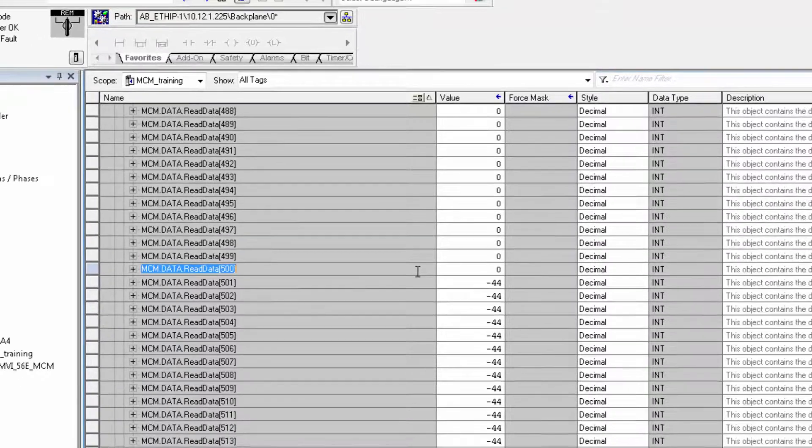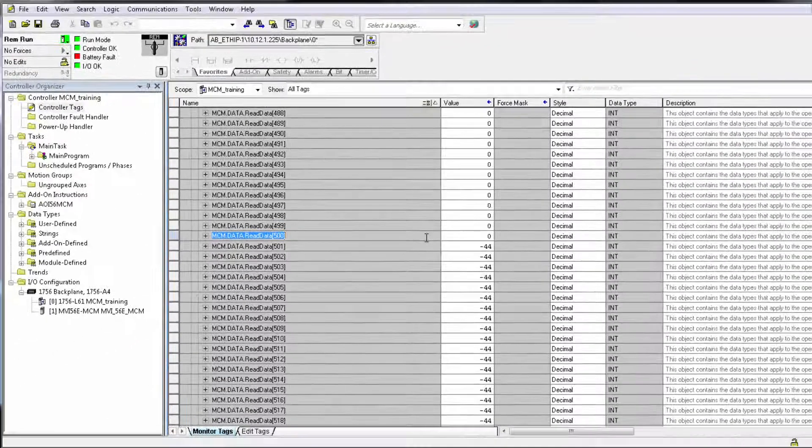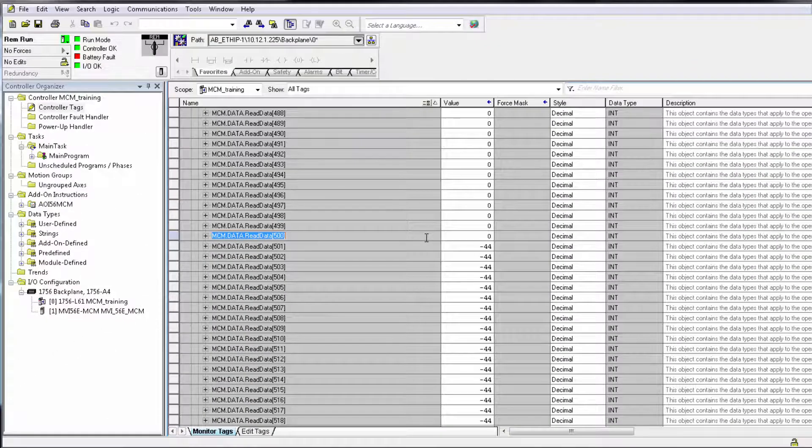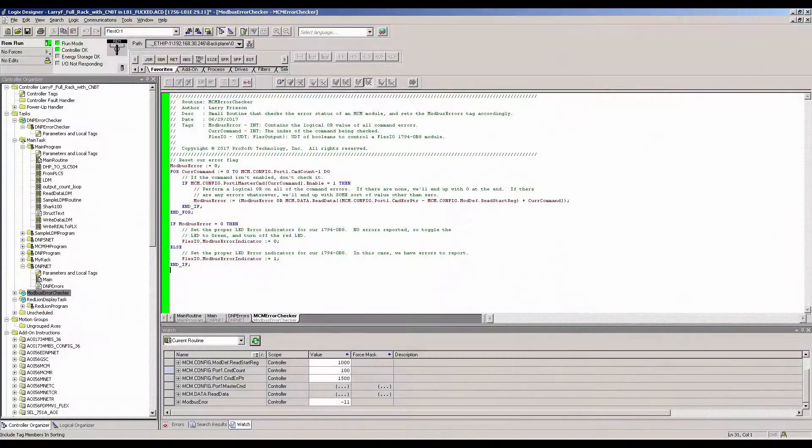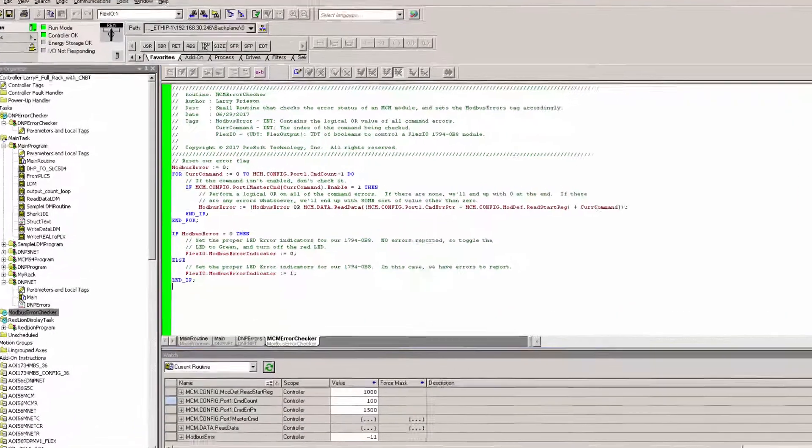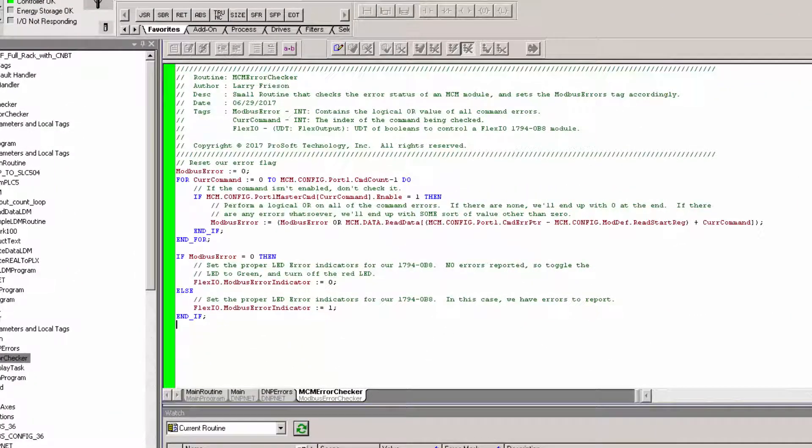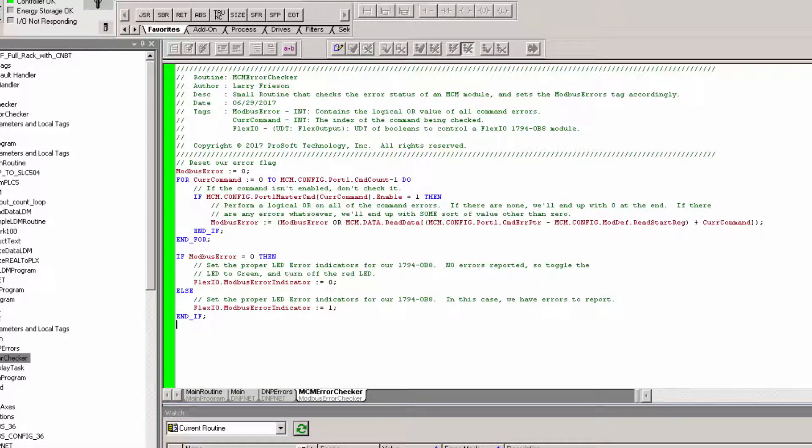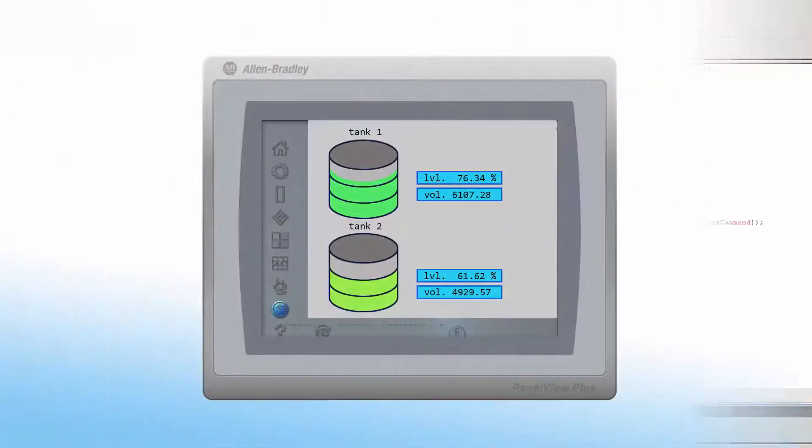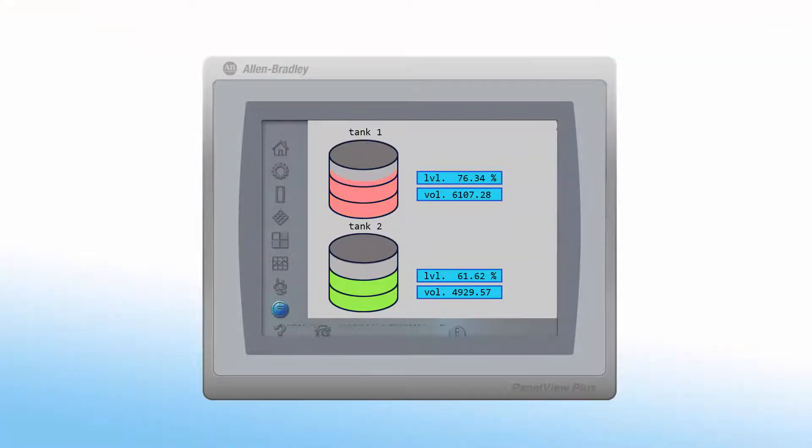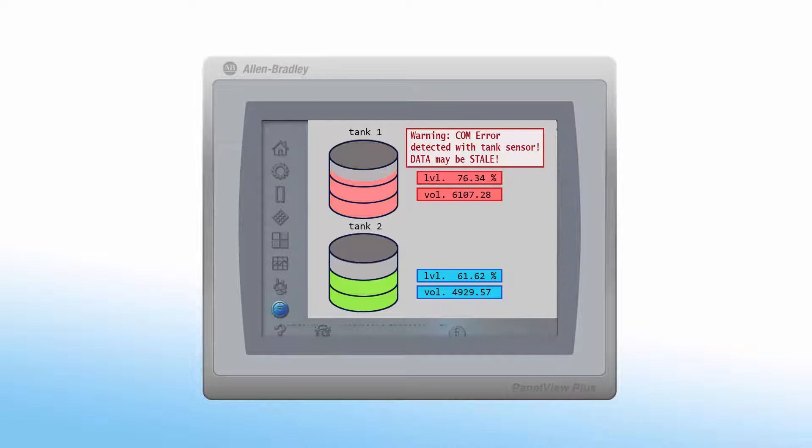Once you have the command error pointer set up, you can write ladder code or structured text to monitor the errors. And if any of them are not zero, an alarm can be sent up to your SCADA to inform that there has been a COM error with a Modbus device or to set a flag on an HMI to alert operators that the values that they're seeing are stale.